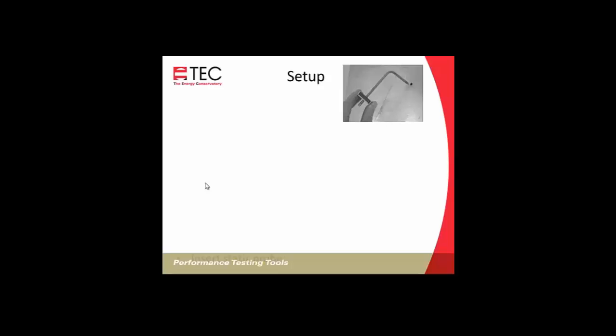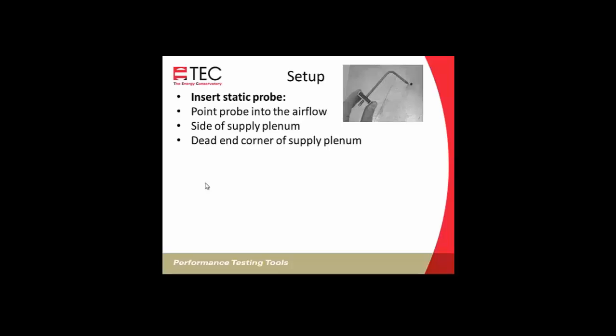And so our setup again, we'll insert the static pressure probe pointing into the airflow. One of the options is to put it on the side of the supply plenum. And side is defined as, for example, with an upright air handler where one supply trunk is coming towards you and another is going away from you, you want to insert it on either the left or right side of that supply plenum, a side where the plenum is not connected. You can put it in a dead end corner of the supply plenum. That's a good place to measure a stable static pressure.